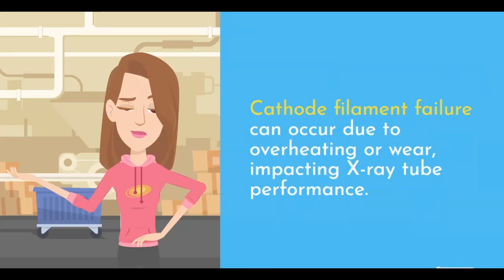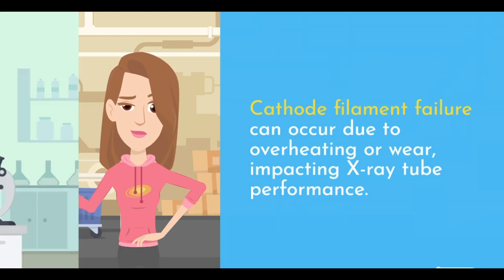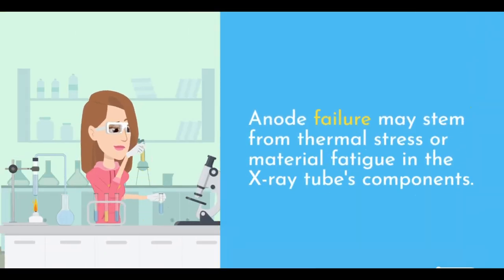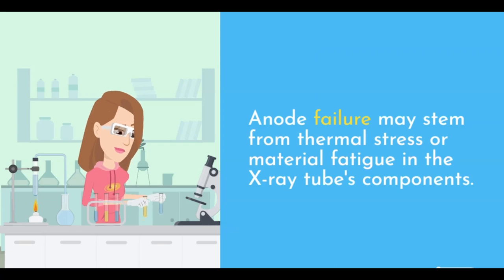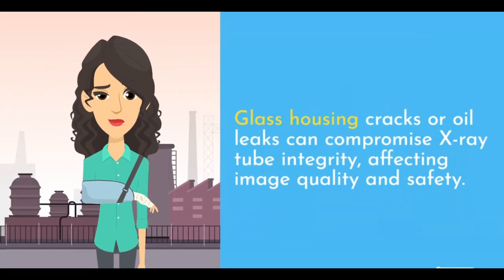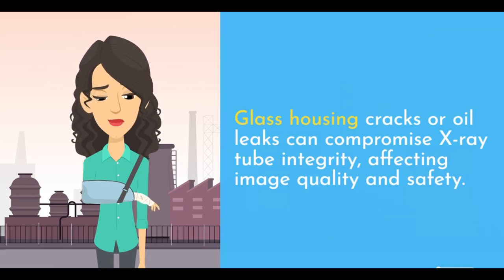Cathode filament failure can occur due to overheating or wear, impacting X-ray tube performance. Anode failure may stem from thermal stress or material fatigue in the X-ray tube's components. Glass housing cracks or oil leaks can compromise X-ray tube integrity, affecting image quality and safety.